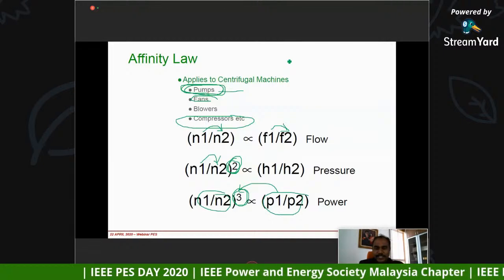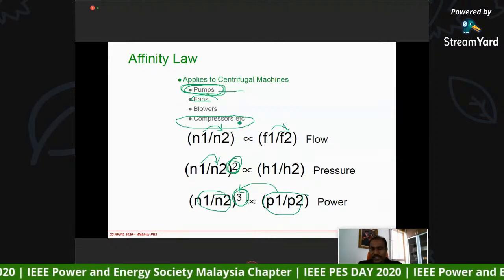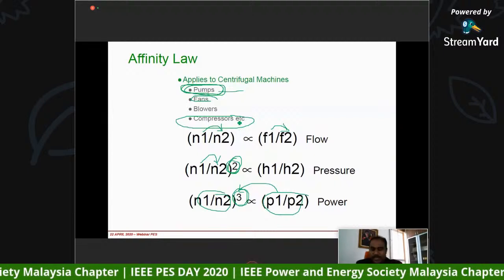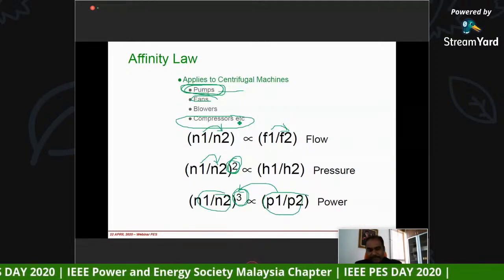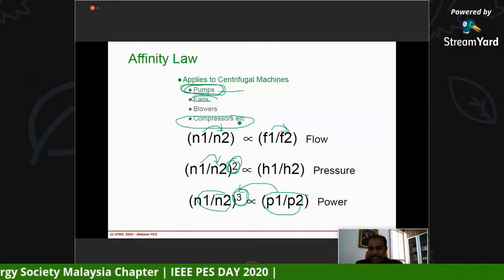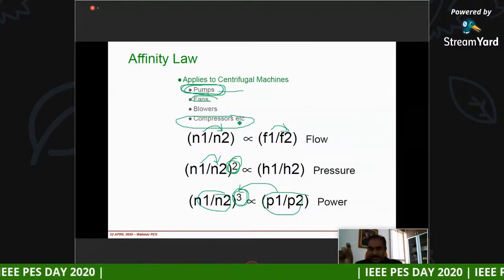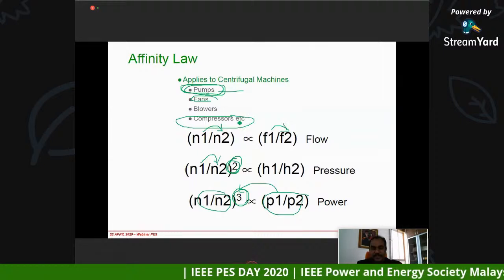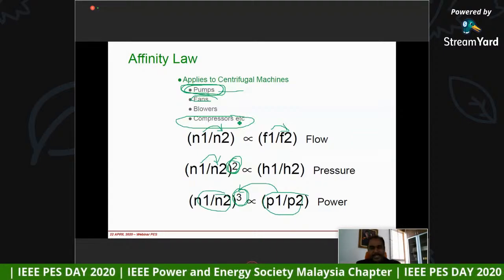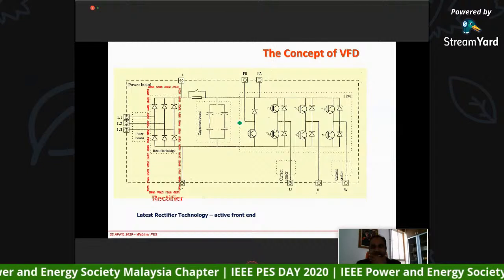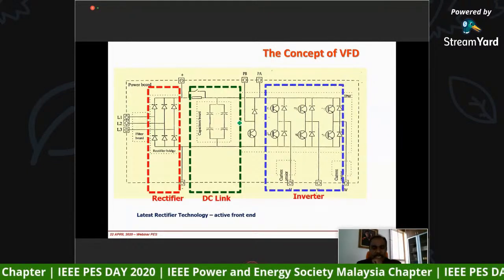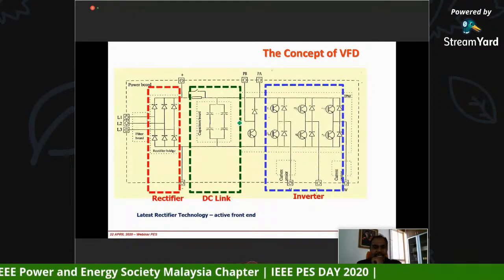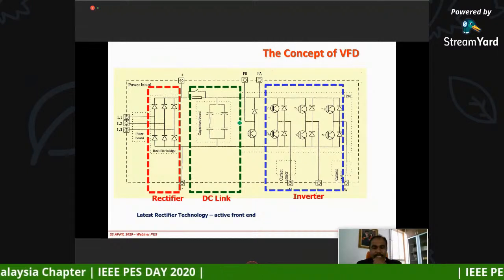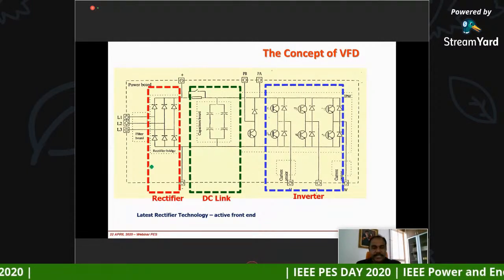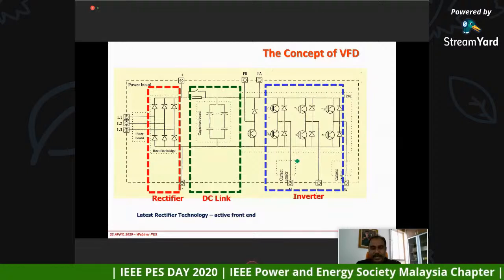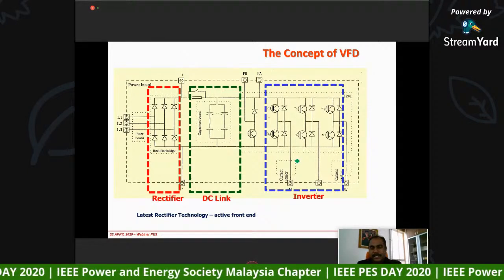That actually gives us another motivation: if there is a need to change the speed, as in the case of a pump system, then we should find a way to reduce the speed by using the variable frequency drive, because there could be a huge amount of savings in the power, or eventually the energy. VFD, I won't go into details, because as you know, it is a typical variable frequency drive. It's completely a power converter. It comprises a rectifier as well as an inverter as the major components. Obviously, there are a lot of other issues.